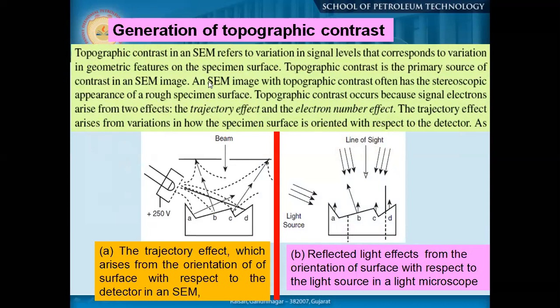Topographic contrast in SEM refers to variation in signal levels that correspond to variation in geometric features on the specimen surface. A SEM image with topographic contrast has a stereoscopic appearance. The topography contrast occurs because signal electrons arise from two effects: the trajectory effect and the electron number effect. The trajectory effect arises from variation in how the specimen surface is oriented with respect to the detector. The electron number effect relates to how many electrons reach the detector.